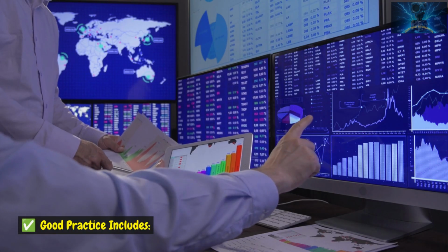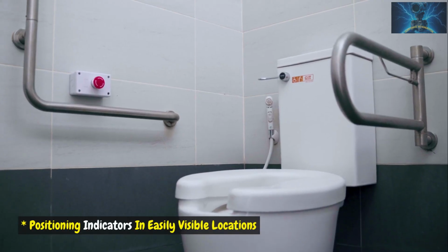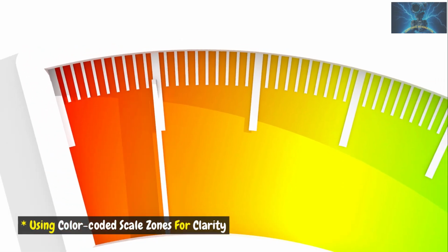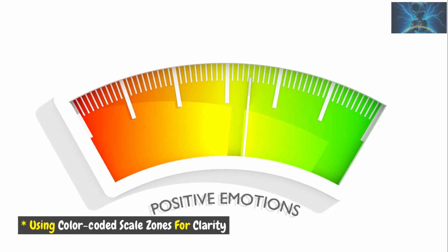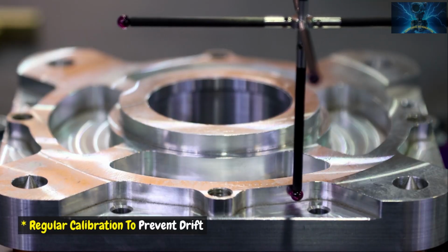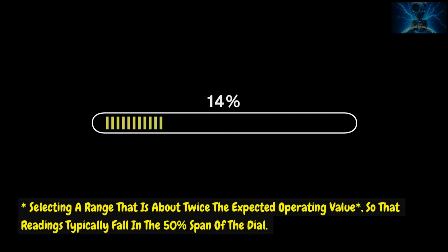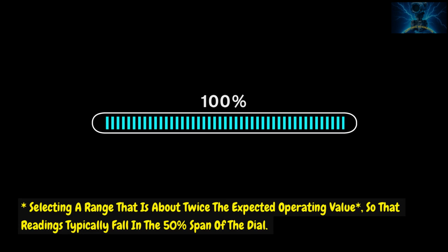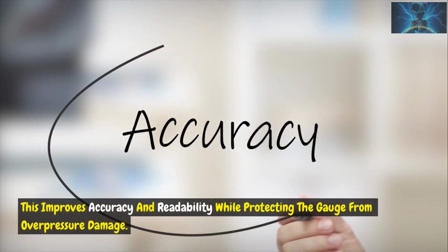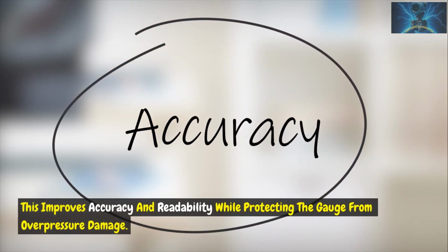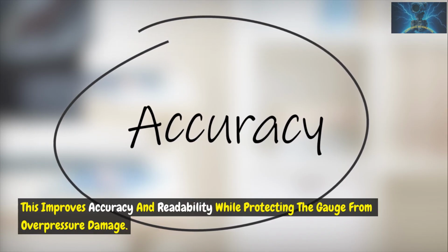Good practice includes positioning indicators in easily visible locations, using color-coded scale zones for clarity, regular calibration to prevent drift, selecting a range that is about twice the expected operating value, so that readings typically fall in the 50% span of the dial. This improves accuracy and readability while protecting the gauge from overpressure damage.